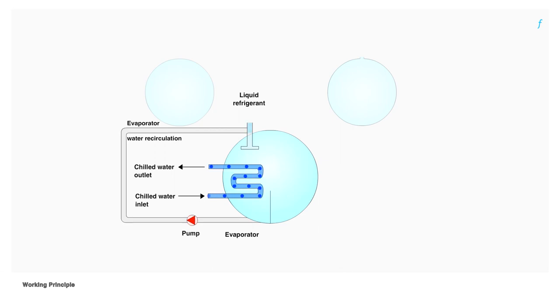When the refrigerant, that is water, enters the chamber maintained at near vacuum conditions, it evaporates. The latent heat of evaporation is gathered from the chilled water circulating in the tubes. This heat loss is reflected as a reduction in the temperature of the chilled water, which enters at 12 degrees Celsius and leaves at 7 degrees Celsius.